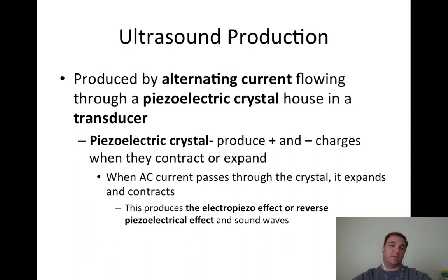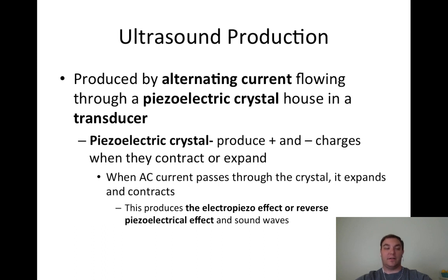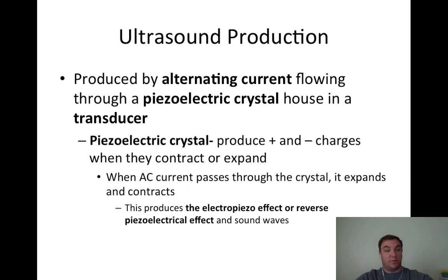Ultrasound production is produced by an alternating current flowing through a piezoelectrical crystal housed in a transducer. The piezoelectrical crystal produces positive and negative charges that cause it to expand or contract. When the AC current passes through the crystal, it literally changes shape, producing the piezoelectrical effect and sound waves. This is what actually produces the wave introduced to the body.